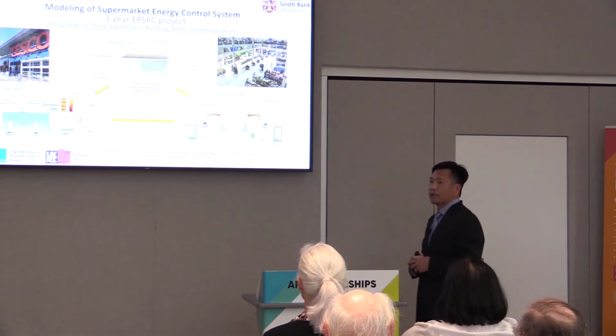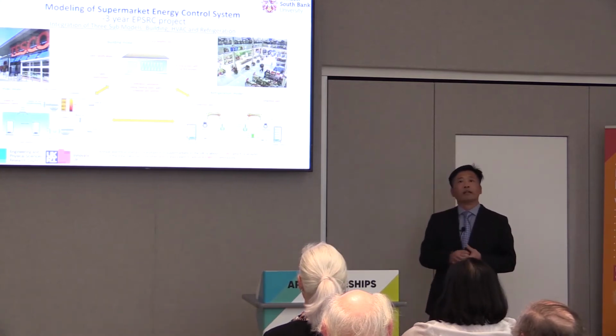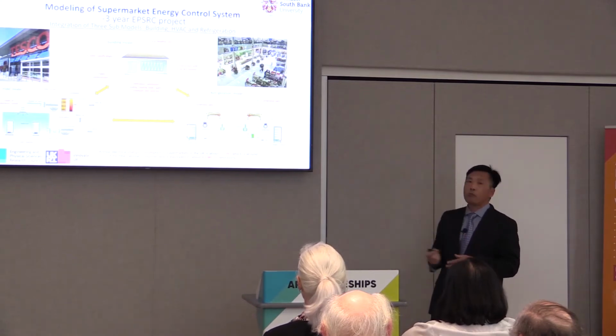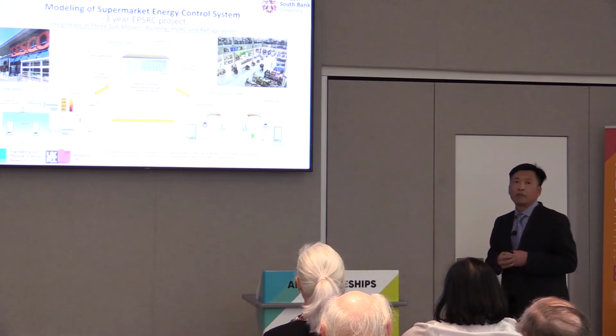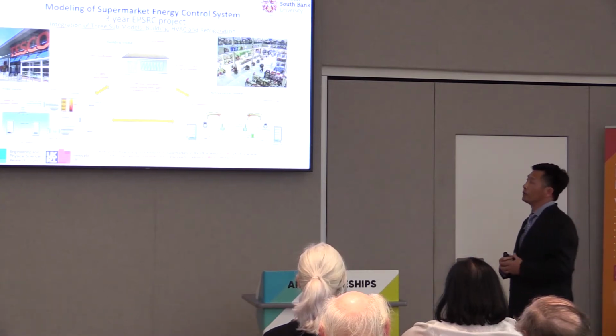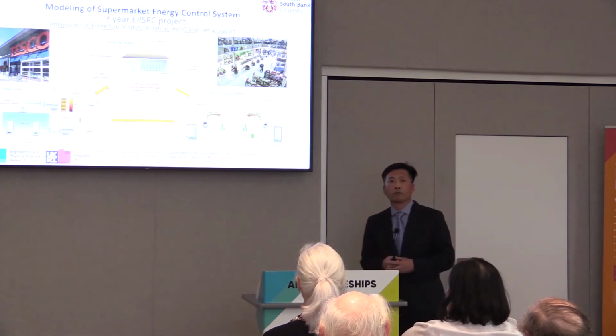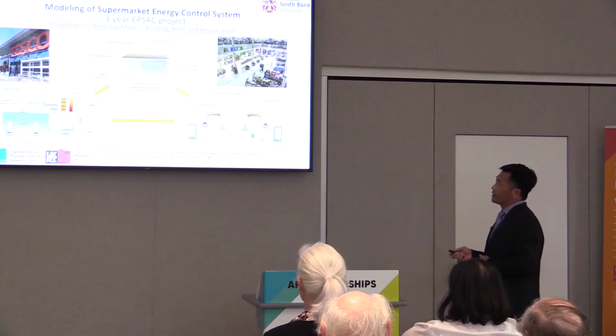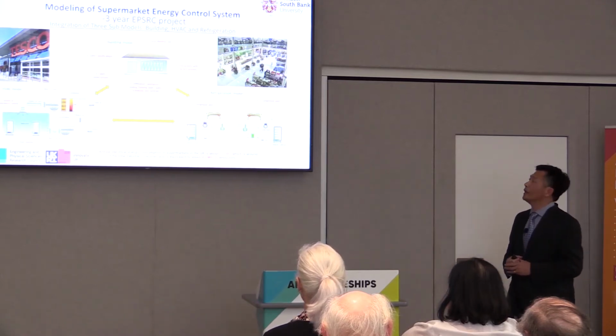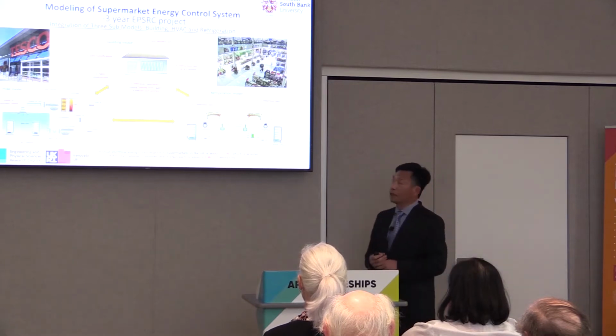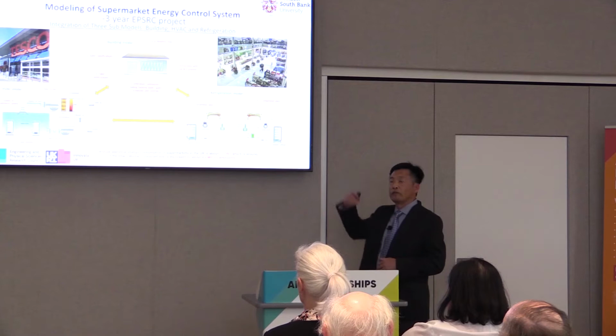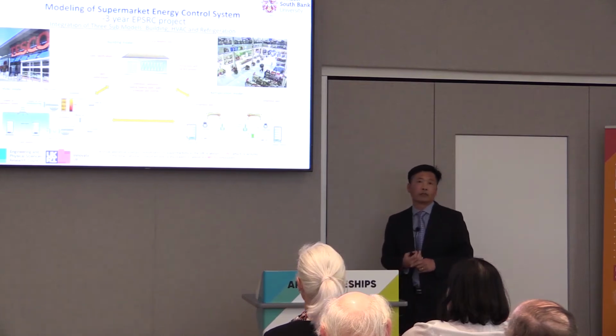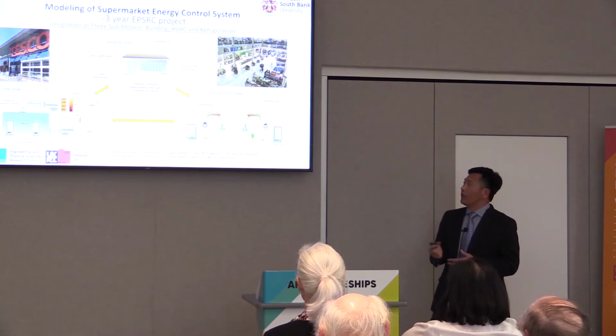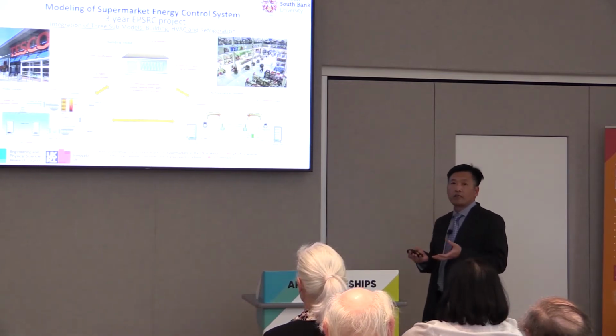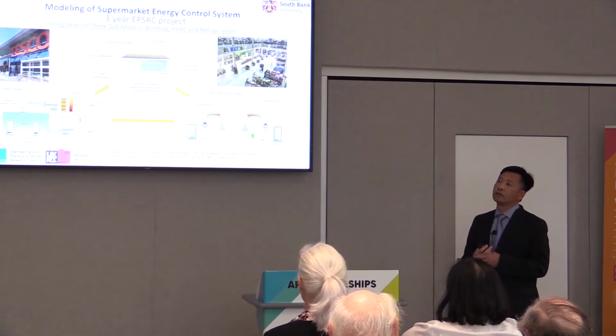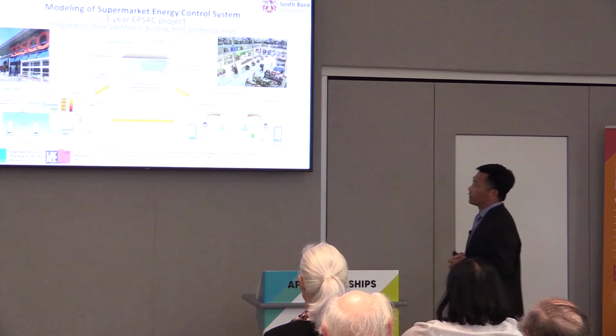And this is the refrigeration system. We know in the supermarket we have chilled food and frozen food. The supermarket normally has 2 independent refrigeration systems. One supplies the cooling for the chilled food, and one supplies the cooling for the frozen food. Each refrigeration system consists of 4 main components: condenser, compressor, expansion, and evaporator. The condenser is normally installed on the roof of the supermarket, and the compressors are installed in a special plant room. The evaporator is installed just underneath each display cabinet, which you can't see from the sales area, to cool down the food stored in the cabinet.